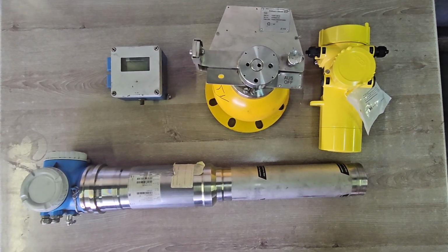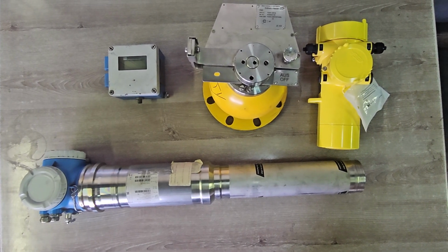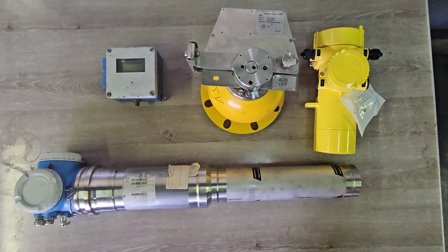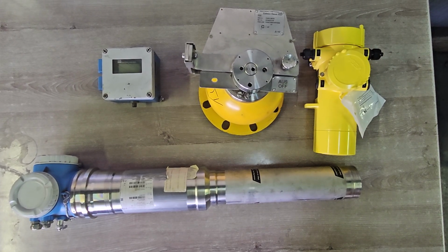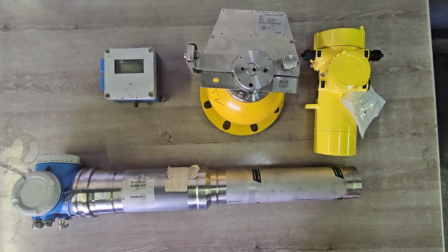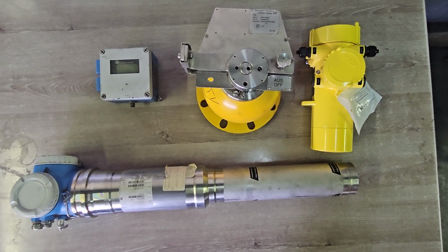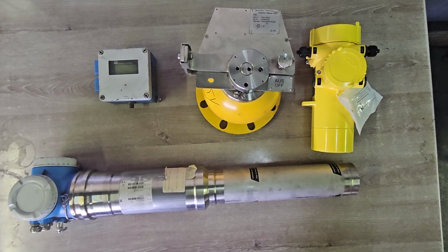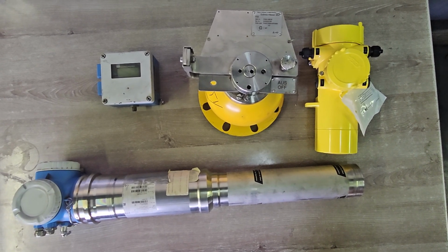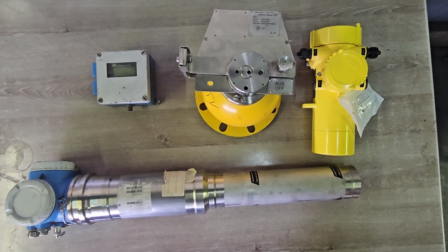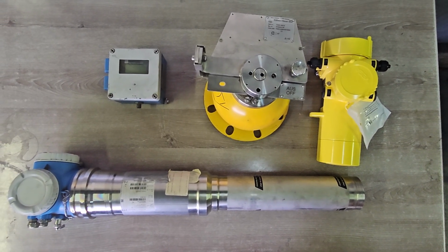So when the vessel is empty, the amount of radiation that passes from one side of the vessel to the other side is at maximum, because there's minimum resistance, maximum flow of energy. But then as the level in the vessel goes up, the amount of radiation that can pass through is minimum and the resistance is higher. That's basically the principle that is being used here.